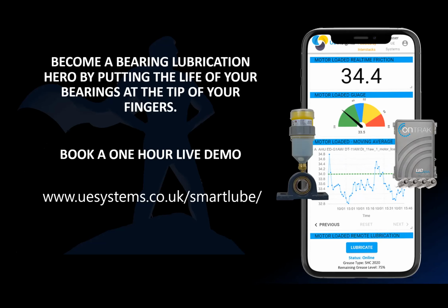Next question: we've had some questions about systems with sealed-for-life bearings—can they use this for just condition monitoring of their bearings? Yes, absolutely. The next part is that they identify a failed bearing, replace it, and start again. Can they input that into the system as an event marking that they've replaced the bearing?